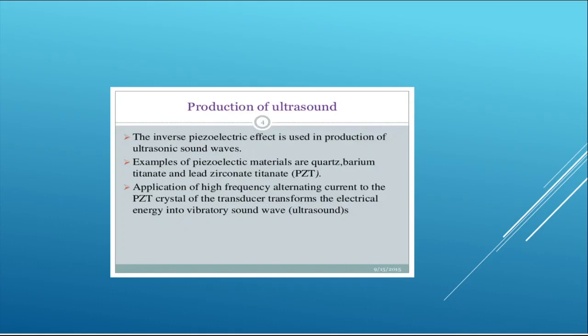For example, the piezoelectric materials are quartz, barium titanate and lead zirconate titanate, PZT. The application of a high frequency alternating current to the PZT crystal of the transducer transforms the electric energy into vibratory sound. That is mainly used in ultrasound therapy. The reverse piezoelectric effect is used. Many types of crystals can be used, but the most favored are those which occur naturally, and some synthetic ceramic materials such as barium titanate and PZT. These crystals deform when subjected to a varying potential difference, which is called the piezoelectric effect.